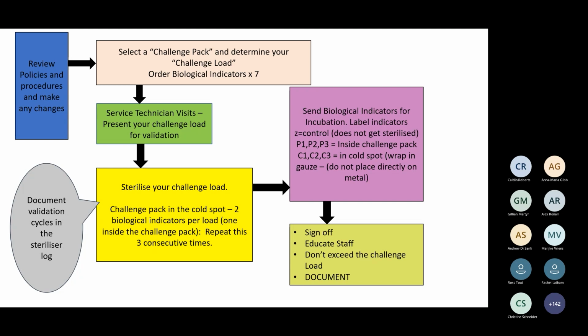Even the one that you're putting in the cold spot, wrap it so it's not sitting directly on your metal trays. You're going to send your biological indicators off for incubation. Label indicators are usually your Z is your control. It doesn't go inside the sterilizer. You don't even process it. And then your P1, 2, and 3 are inside your challenge packs. And then your C1, 2, and 3 are in your cold spots. So P1 and C1 will go in your first sterilization load, P2 and C2 in the second, P3 and C3 in the third.